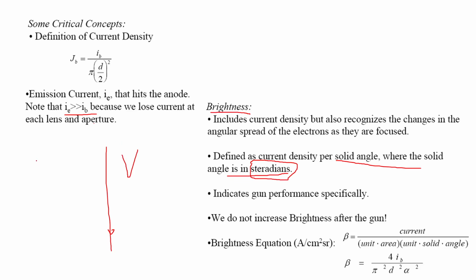I told you that these are pin kind of sources. After a certain time they can either break in between, so it will not give a good quality signal, or there could be damage at the source from where the electrons are being produced itself. So this brightness term can tell about the performance of the gun.